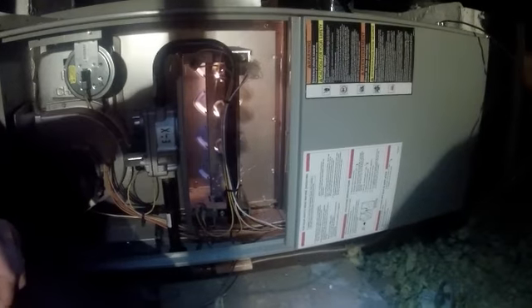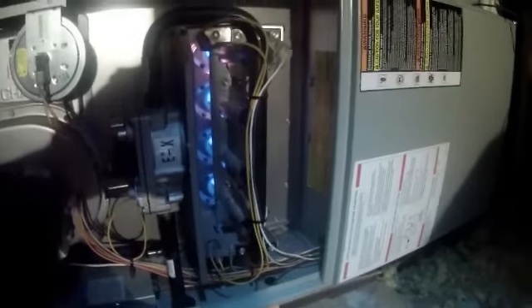Okay, so now we have zone 1 downstairs and zone 2 upstairs wired up. Now we just need to hook in the dampers that actually open and close for the airflow upstairs and downstairs. Okay, we got both zones open now, both zones on. System is up and running. Now we gotta do some airflow checks.